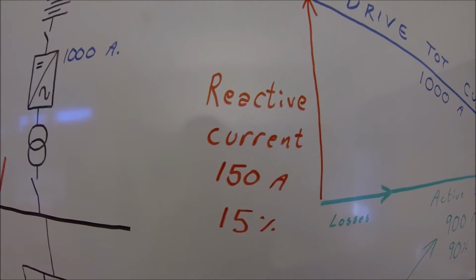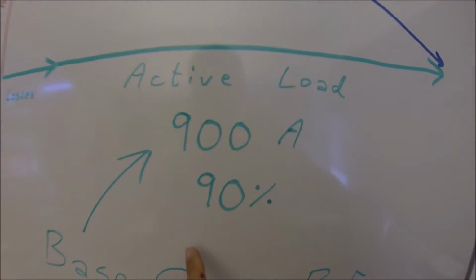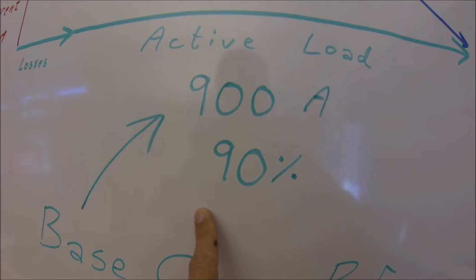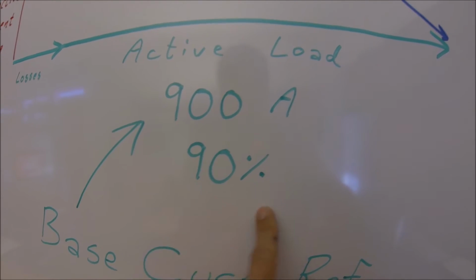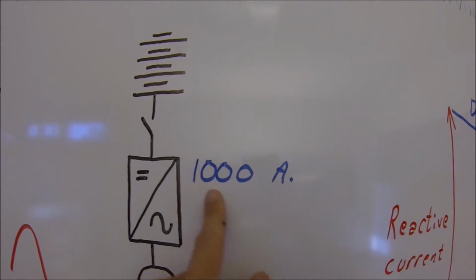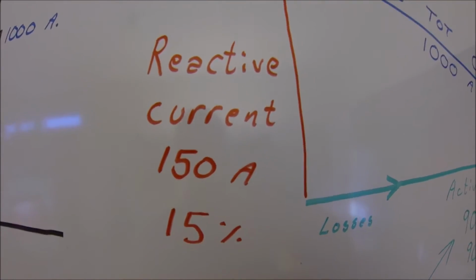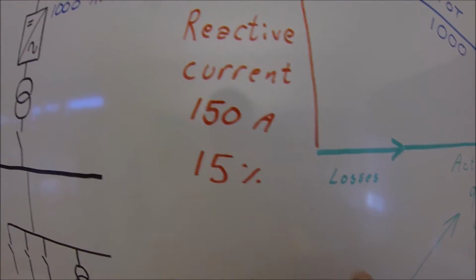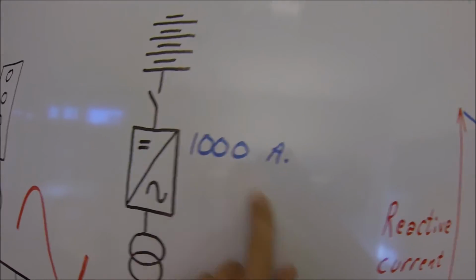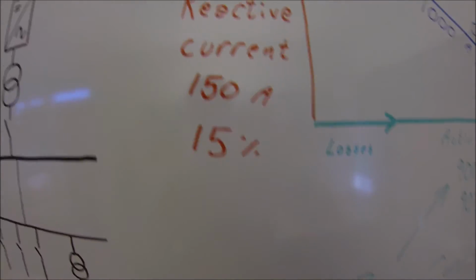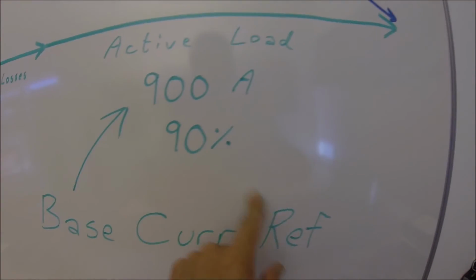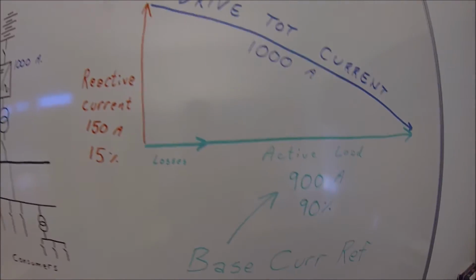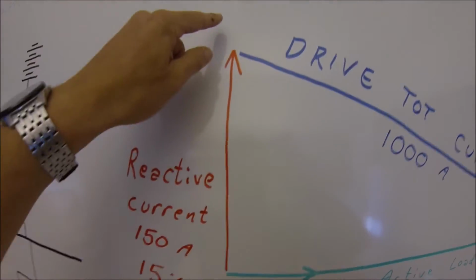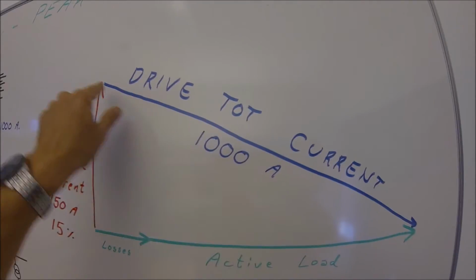When talking about the reactive current and active current, we often use a percentage value. This percentage is a percentage of the drive nominal current rating. So 150 ampere on the reactive current means 15% of my IGBTs are used now for handling the reactive current. 15% and 90% doesn't add up to 100% because, well, it's vector summarization.